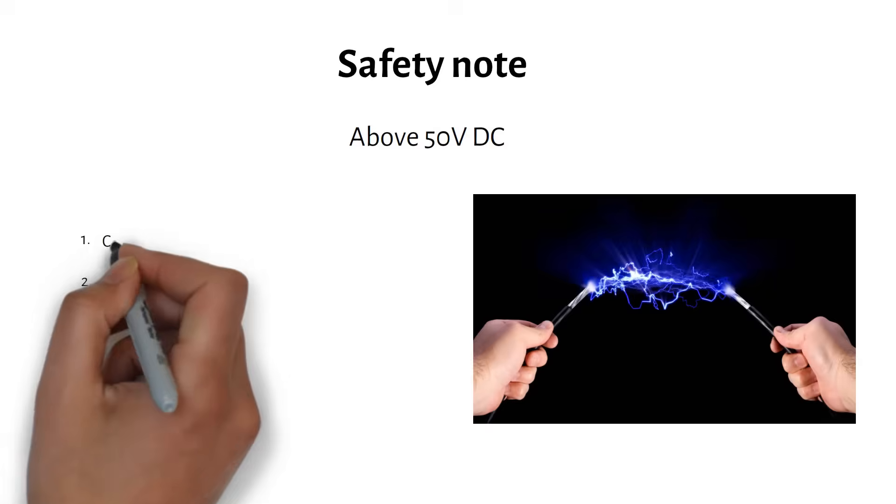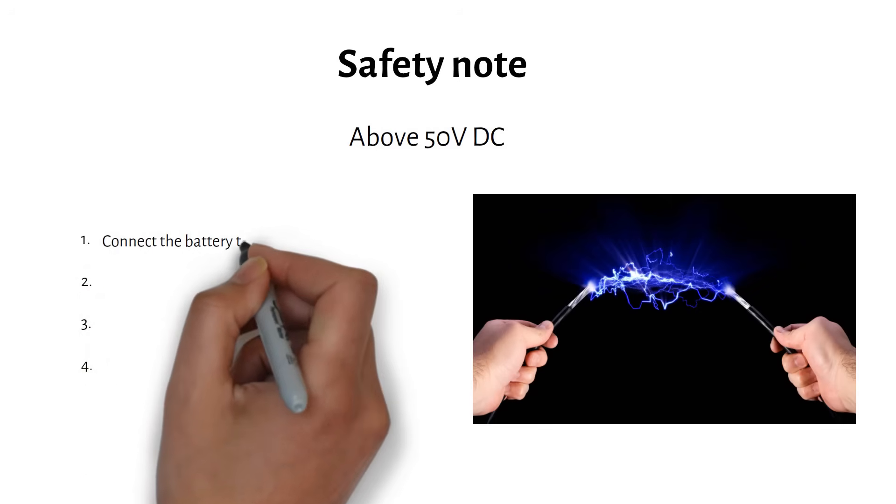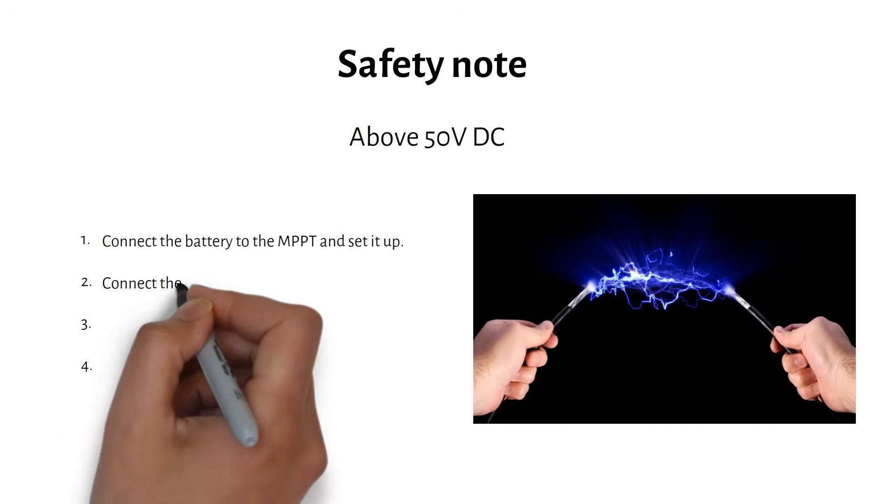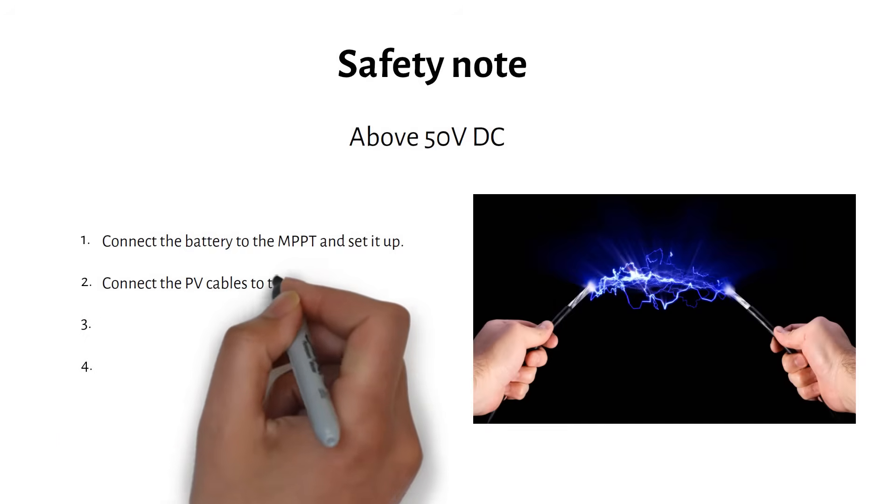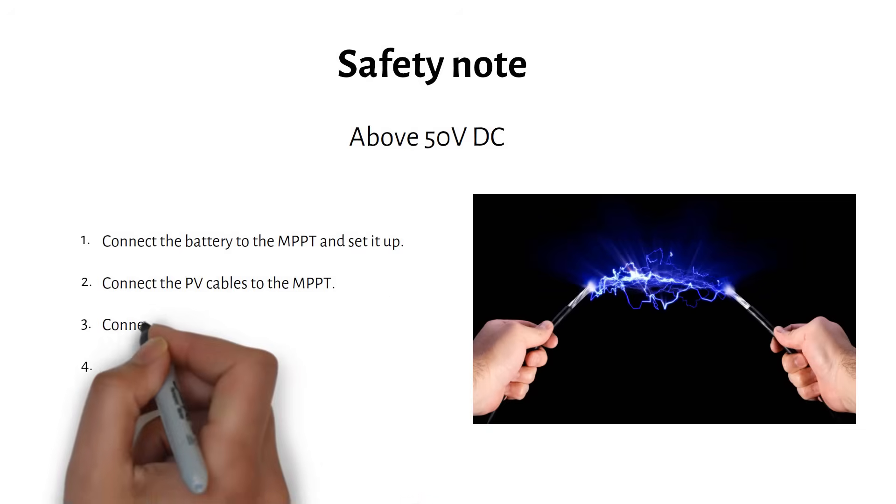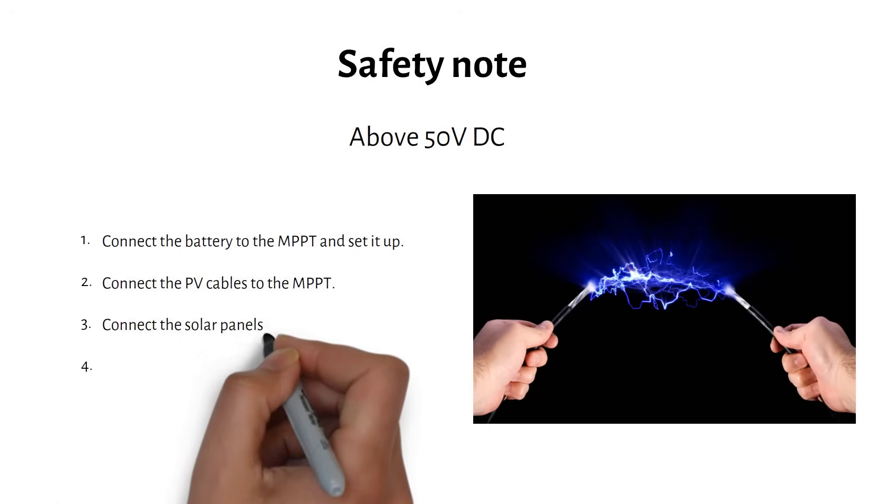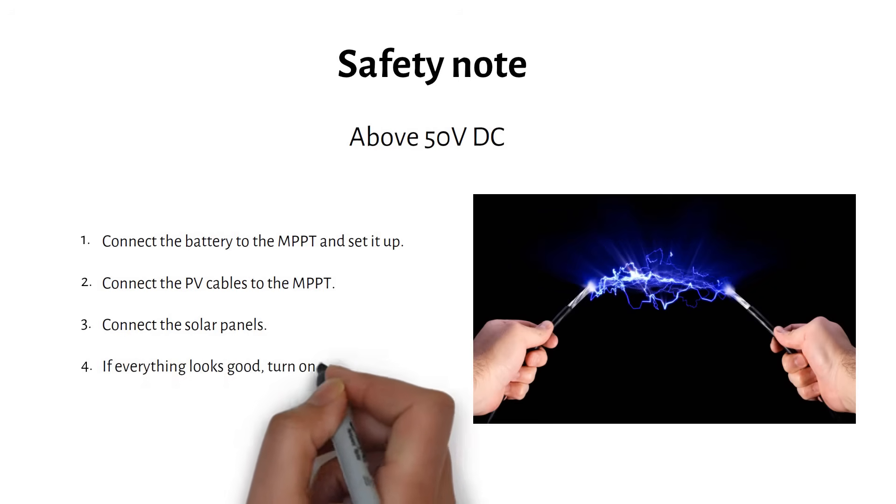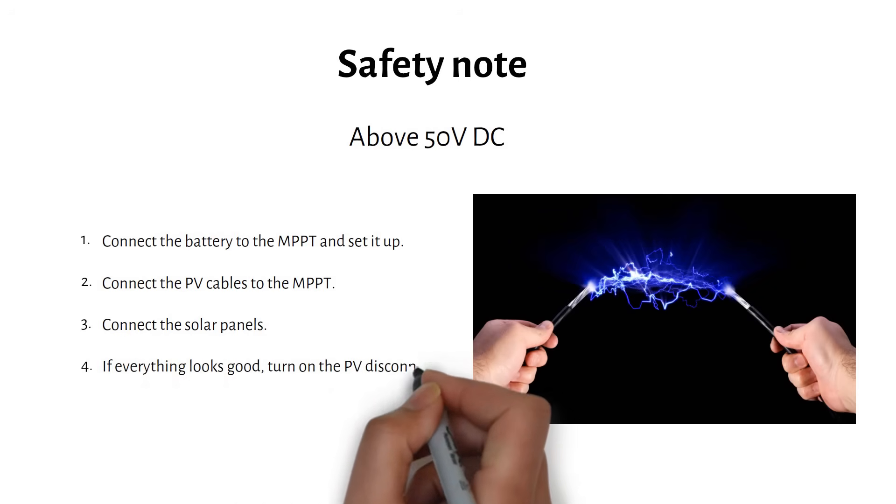So to make it safe, follow these steps. Connect your battery to the MPPT and program it. Then connect the PV cable to the MPPT without connecting your solar panels. Then connect your solar panels, measure the voltage and the polarity with a multimeter. If everything is correct, turn on the PV disconnect switch. Respect the maximum PV input voltage and input current ratings from the MPPT datasheet. And don't work on live PV strings.